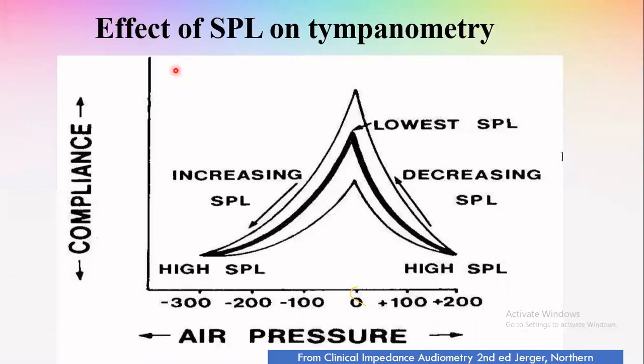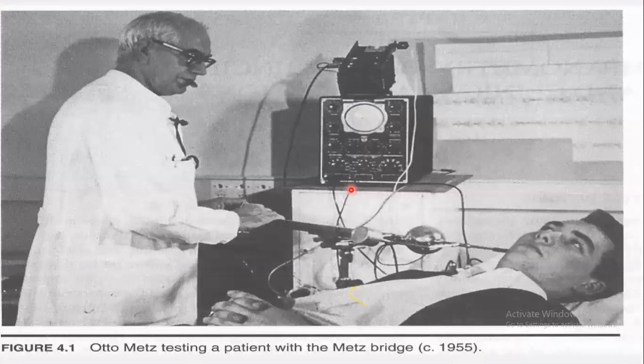We use 85 dB SPL for the probe tone because if you use higher SPL — above 85 or 90 dB — it might activate the stapedius muscles. Some resources mention using as low as 70 dB. If higher SPL is used, the compliance value will be reduced, confounding the measurement.